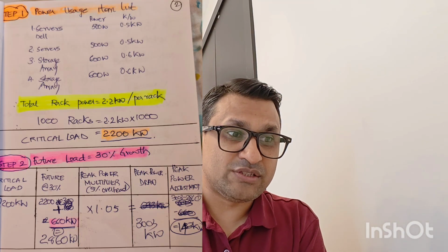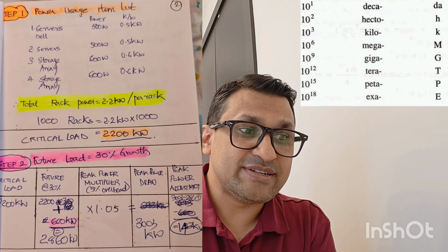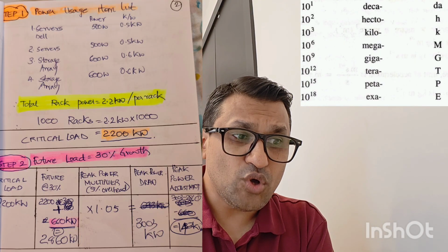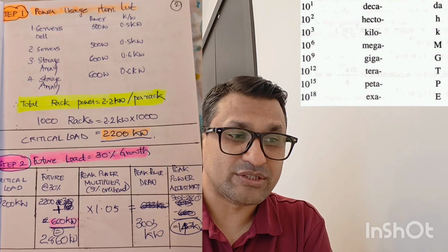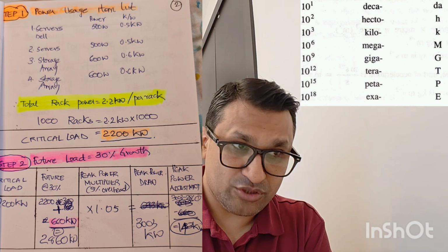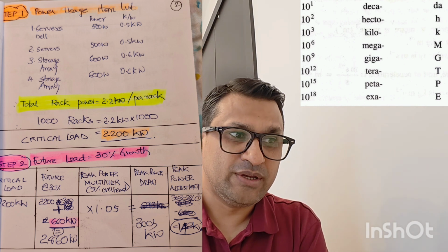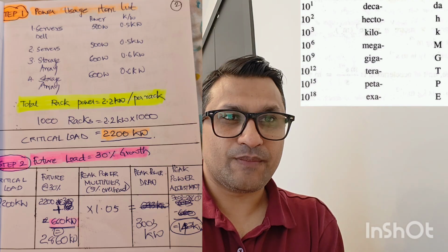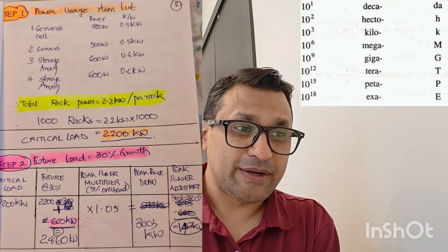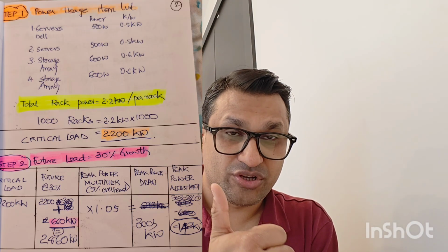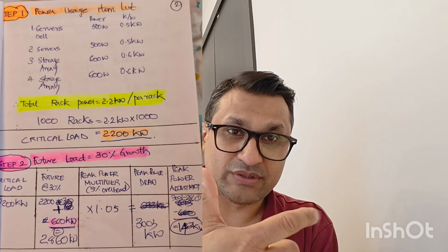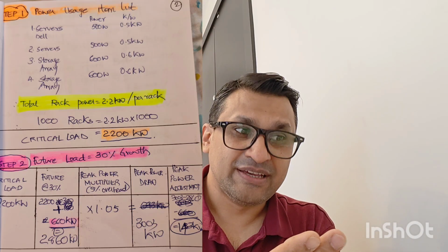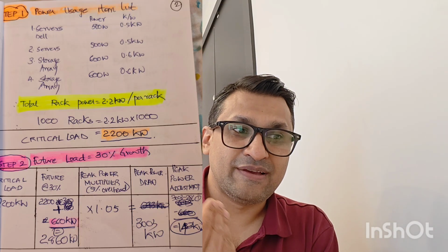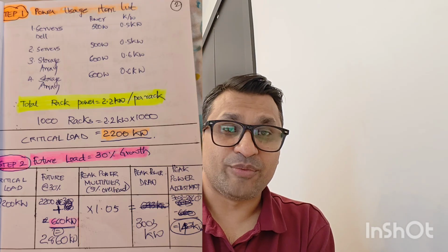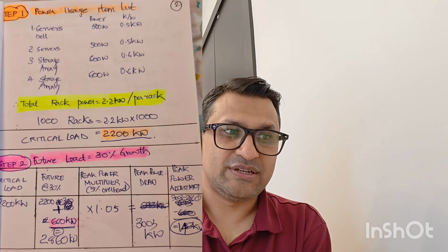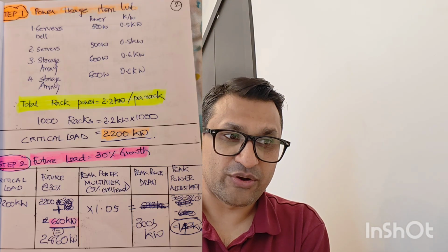So that will give us 2,860 kilowatt or 2.86 megawatt. That's the future load, including the critical load. The future load with the 30% addition: the original critical load was 2200. You're adding the future load of 30%, 660. 2200 plus 660 is 2860. It's going to be 2.86 megawatt. That's the total load, critical load, including the future.